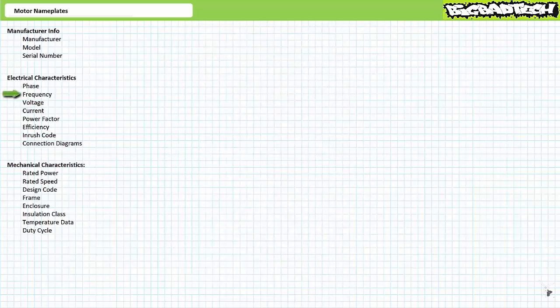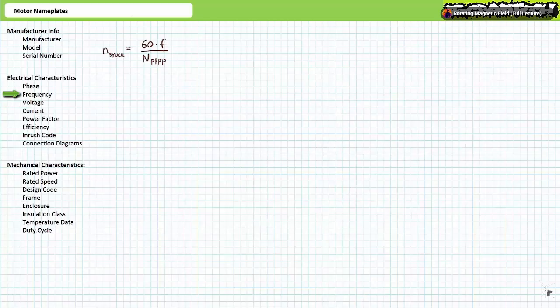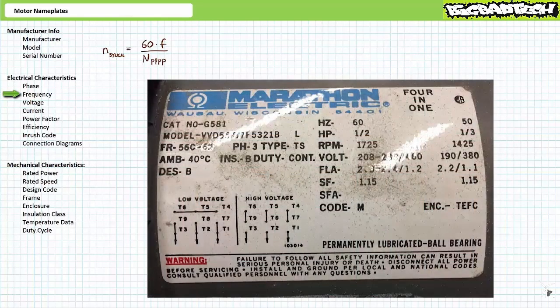Frequency. The frequency entry specifies the excitation frequency the motor in question is intended to operate with, ordinarily 60 Hz in the US and Canada, and 50 Hz in the EU. All entries in the motor nameplate are specified at this particular excitation frequency. As we learned in the rotating magnetic field lecture, available at the Big Bad Tech channel, synchronous speed, the speed of the stator rotating magnetic field, is directly dependent upon excitation frequency. Motors operated at a higher frequency rotate faster, whereas motors operated at a lower frequency rotate slower. Related to this fact, some motors can be used in both 50 Hz and 60 Hz systems. If so, a manufacturer often splits the entries on a motor nameplate to specify properties at 50 Hz and again at 60 Hz.